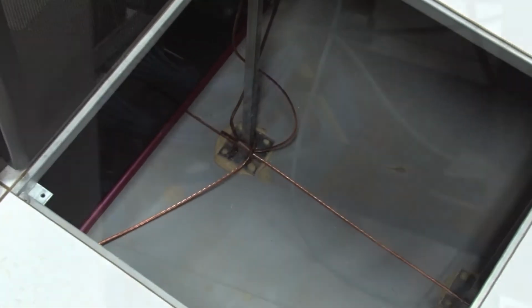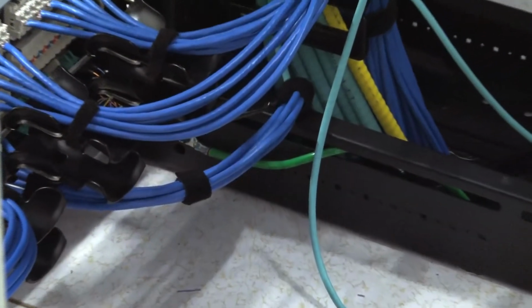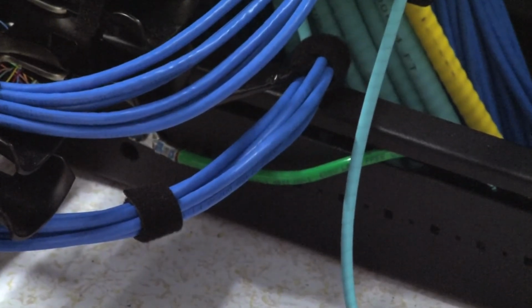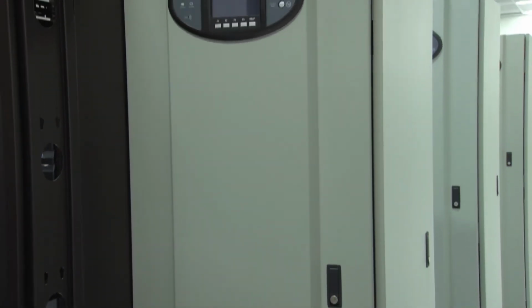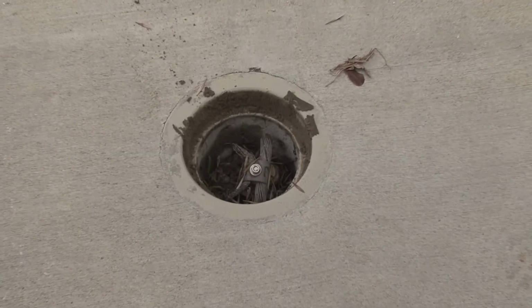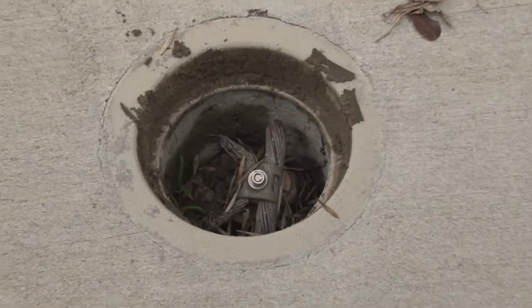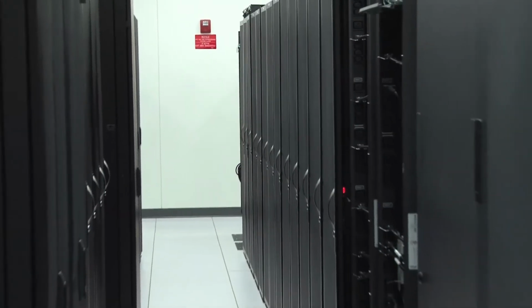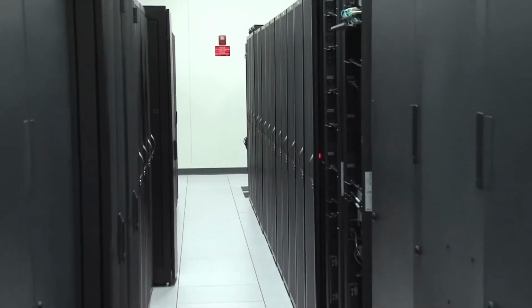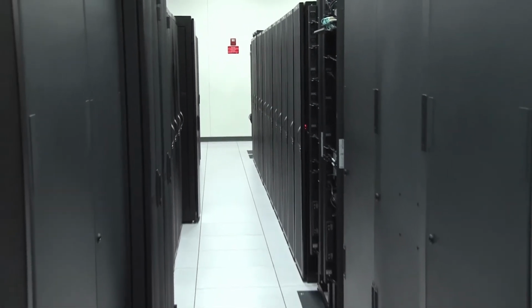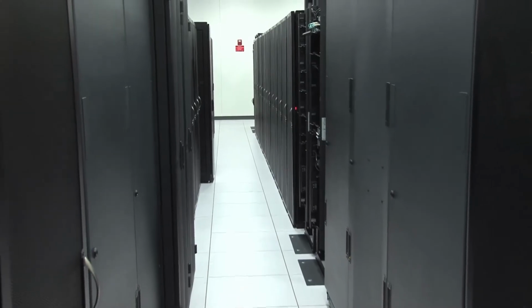On a data center floor, every 4 foot a pedestal is grounded. So we have a number 4 wire gauge bare copper underneath the floor that's in a 4 foot pattern. Each rack then is grounded to that 4 foot ground path. Each remote power panel is grounded to that as well. All the ground paths go back to one deep earth ground. You have to watch your dew point inside a data center, and that's really a lot of the reasons why we're also grounding these racks: to protect that sensitive equipment from static electricity.